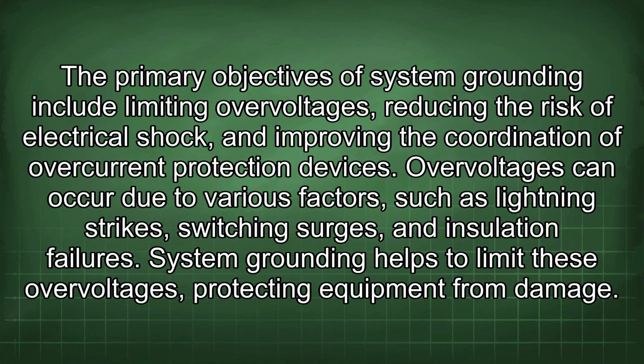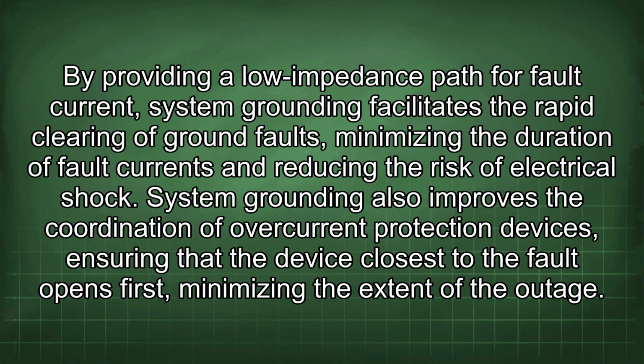The primary objectives of system grounding include limiting overvoltages, reducing the risk of electrical shock, and improving the coordination of overcurrent protection devices. Overvoltages can occur due to various factors, such as lightning strikes, switching surges, and insulation failures. System grounding helps to limit these overvoltages, protecting equipment from damage. By providing a low impedance path for fault current, system grounding facilitates the rapid clearing of ground faults, minimizing the duration of fault currents and reducing the risk of electrical shock. System grounding also improves the coordination of overcurrent protection devices, ensuring that the device closest to the fault opens first, minimizing the extent of the outage.